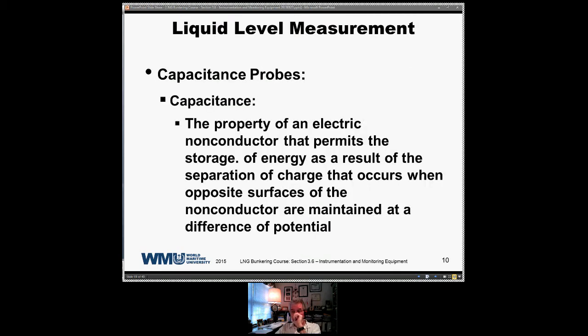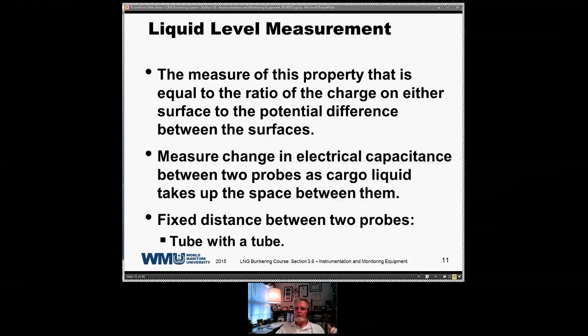Capacitance probes were used early on in projects. They are very accurate. No moving parts. That's a nice thing about a capacitance probe. So, the property of an electric non-conductor that permits storage of energy as a result of the separation of charges that occur. This is complicated. The opposite surfaces of a non-conductor remain in a difference of potential. Basically, it's a tube within a tube, and you're measuring an electrical potential difference between the two tubes, and that changes as the liquid rises inside that tube. The input from that is transferred over to an analog to digital converter, and it comes out and gives you a level.